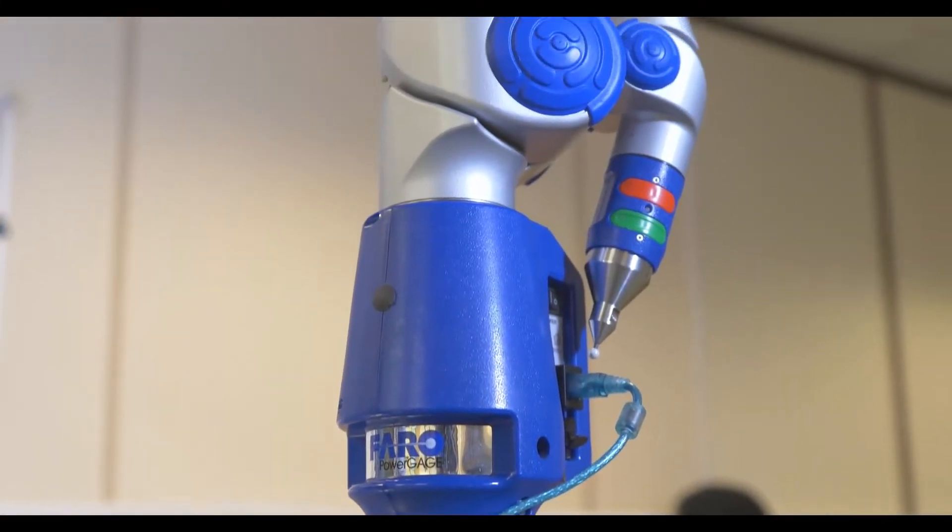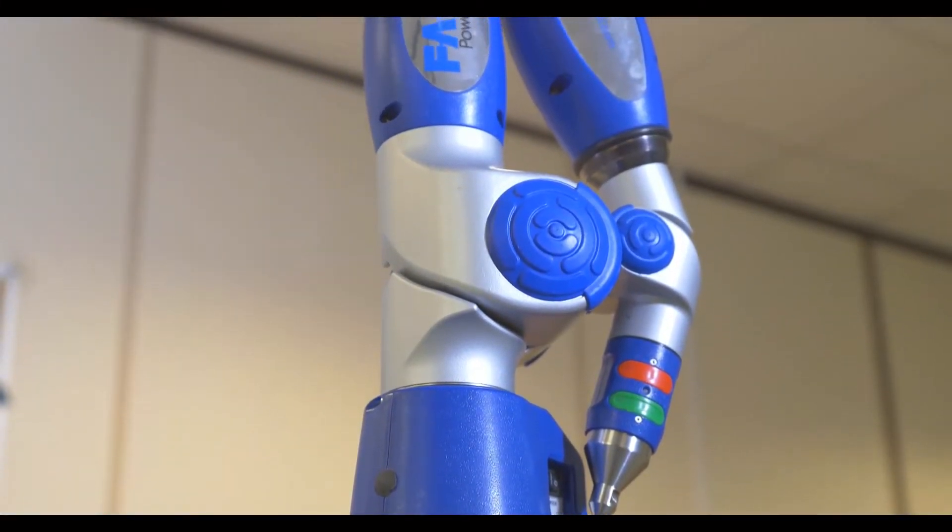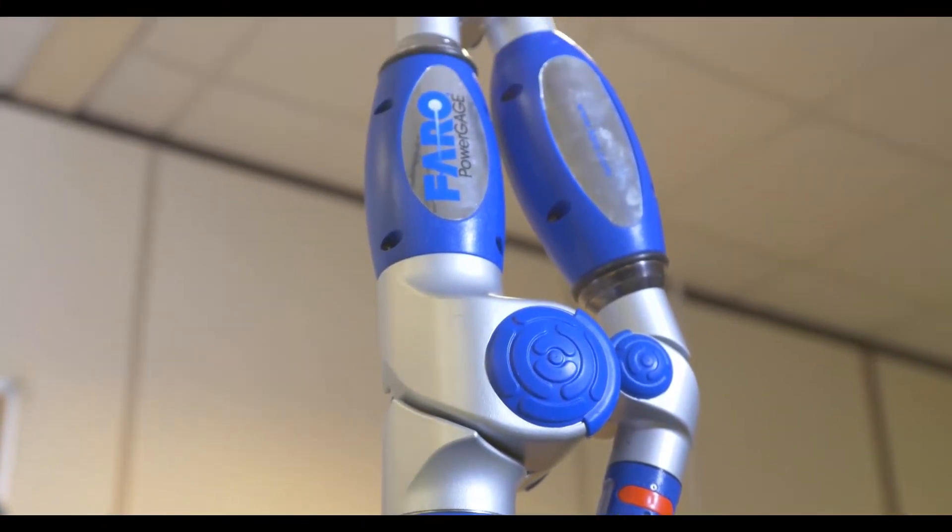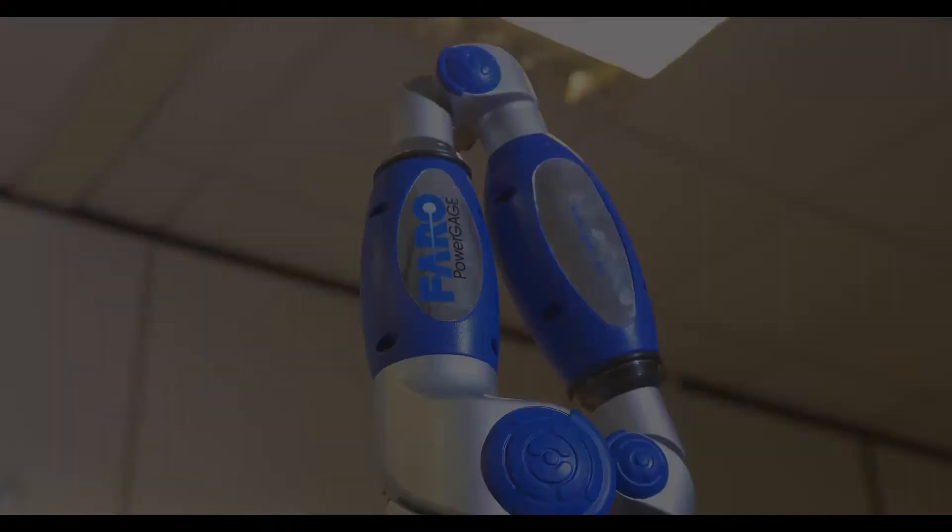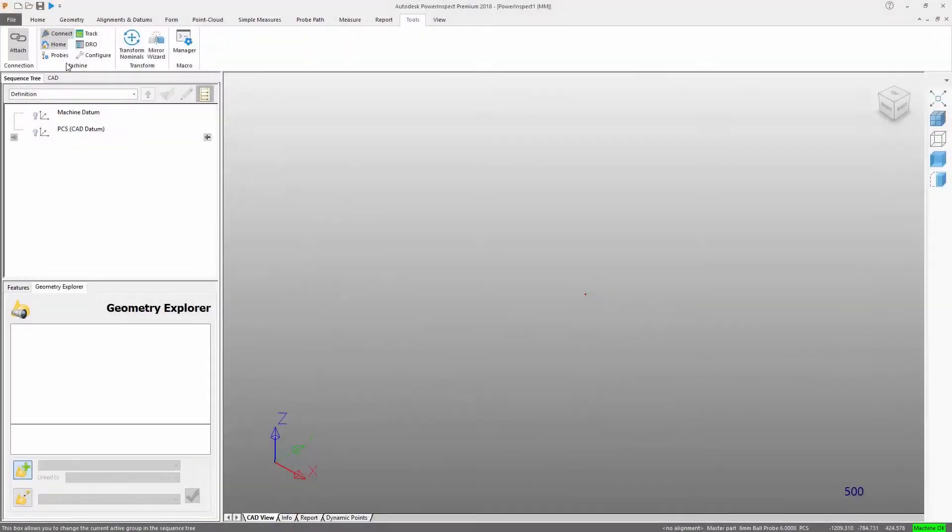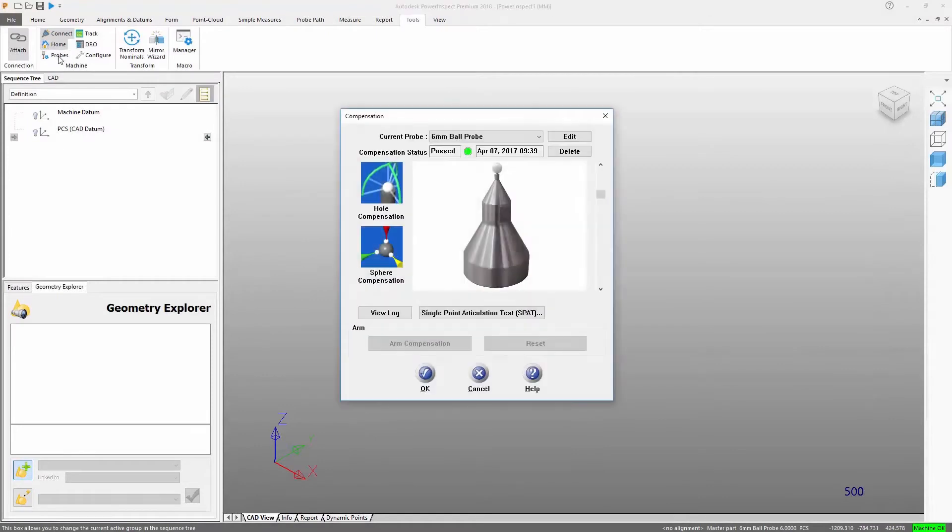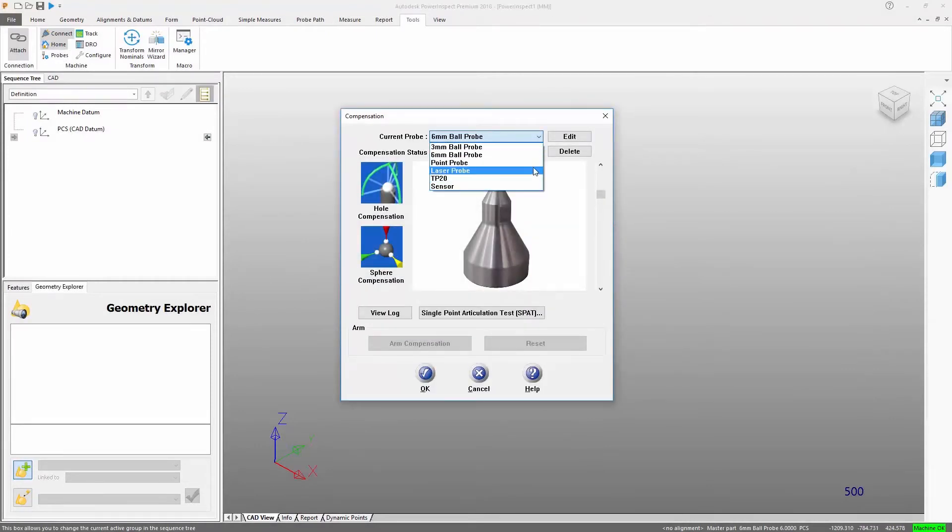This same inspection sequence could just as easily be measured using an articulated arm. Just select the correct protocol from the list, set the probe that is going to be used, then attach the document to the device to begin measuring.